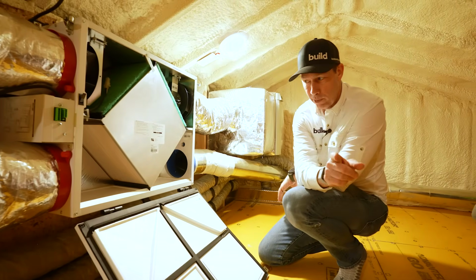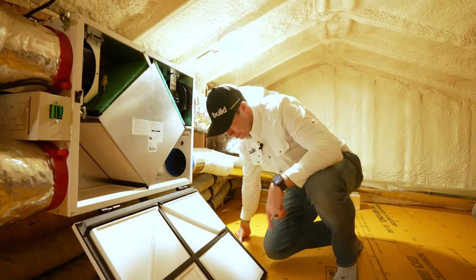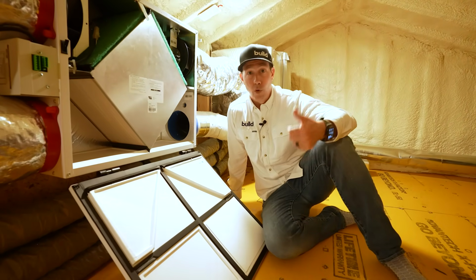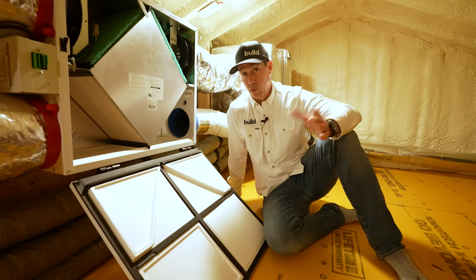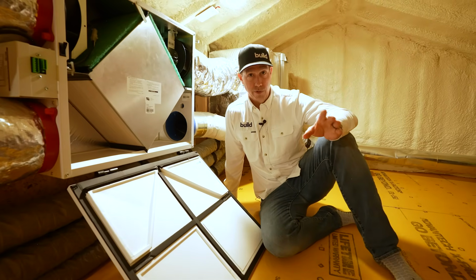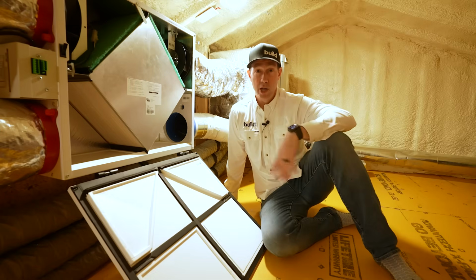I do want to say though, remember whatever the manufacturer tells you about filter changes, that's a guess from them, right? If that manufacturer's in Switzerland or Michigan and tests it, that's a whole different deal than Texas or wherever you're watching this. So remember that filter changes are a general guideline, not gospel advice, right? So I'm going to tell my homeowner, hey, this is probably a 6-month filter change, but we should check it every 3 months and see.